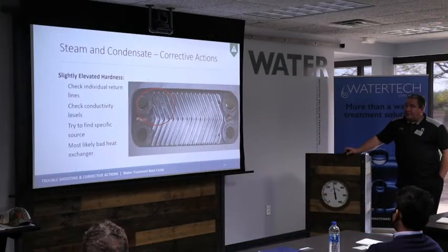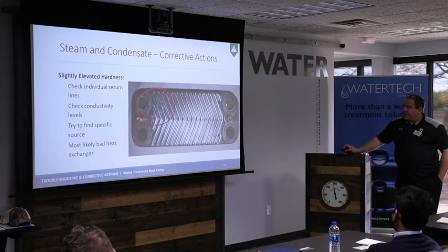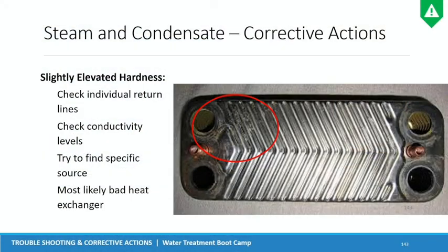Another reason, when we talked about this a little earlier, is that you could have a heat exchanger where you're using steam on one side, heating it, and then your seals start failing on your heat exchanger. If these fail, depending on it, either A, it could be process contamination, or B, if it's water to water or steam to water, eventually something's going to give and it will likely contaminate the condensate system. So by monitoring the condensate system, they can tell you if something else is contributing to the poor condensate quality.